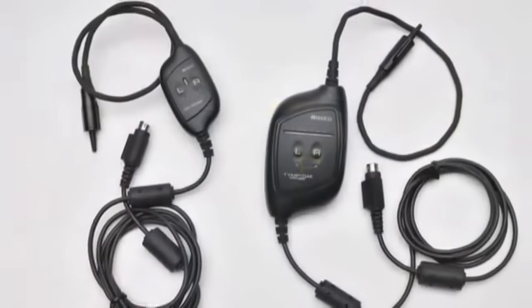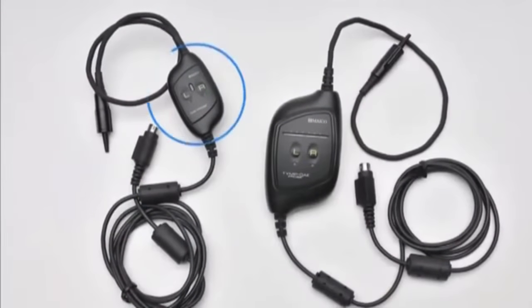The external probes also have an amber or blue light under each button to indicate the ear being tested, as well as a status indicator. The green status light means that the probe has been detected by the Ero Scan Pro and is ready to test. A flashing yellow status light indicates that auto start is in progress, and a solid yellow means that a test is in progress. Of the two external probes, the OAE probe offers the same TE-OAE specifications as the internal probe, while extending the DP-OAE range from 6 to 12 kHz.